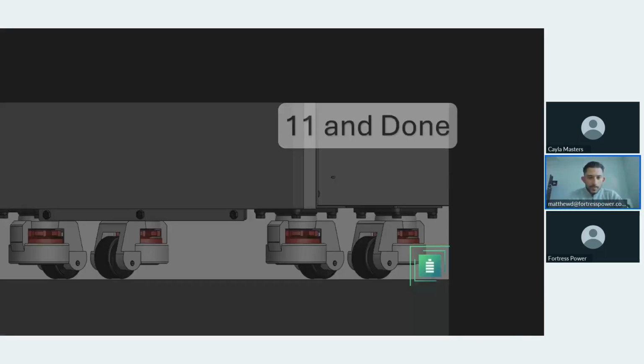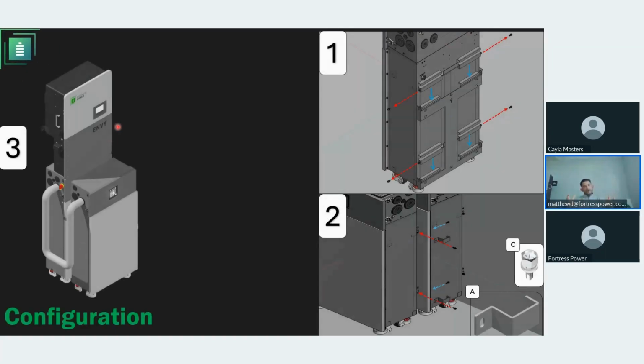Now for this configuration where you're stacking the battery in front, what we typically suggest is using liquid tight flexible conduit to go from one side of the E-way to the other side of the E-way. This will facilitate anything that needs to be done to get back to the other E-way. So if servicing needs to happen, this will allow me to take the brackets from the second battery right in front and move the battery without so much hassle, because it has wheels included. So yes, we recommend using flexible conduit.